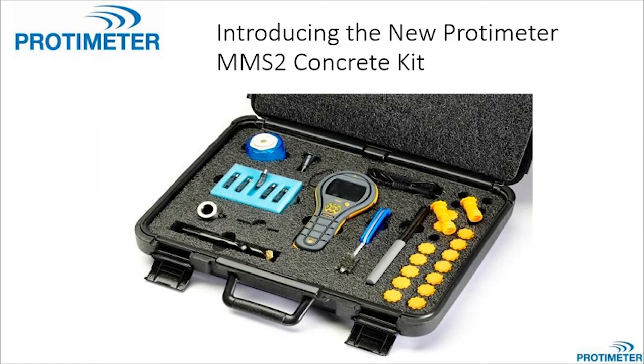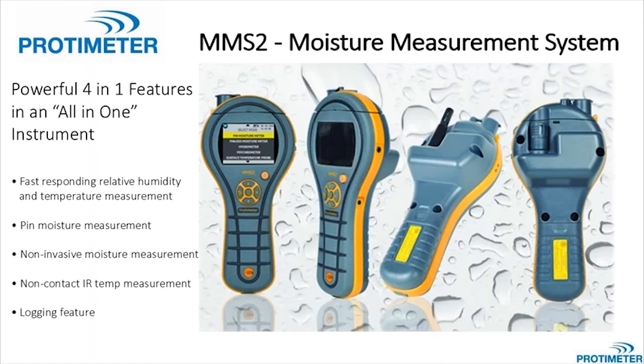Since the MMS2 is the foundation of the kit, I wanted to go over some key benefits of that meter prior to getting into the concrete test procedure. The MMS2 is a very powerful all-in-one instrument. It ranges in function from pin to pinless and hygrometry, so you can get an idea of your moisture in materials as well as an indication of what's going on in your ambient environment with regard to relative humidity and temperature. This meter also incorporates an infrared surface temperature sensor. All these features will be used when conducting the ASTM F2170 concrete test, so keep these in mind as we go through, because we will apply them to the concrete test.